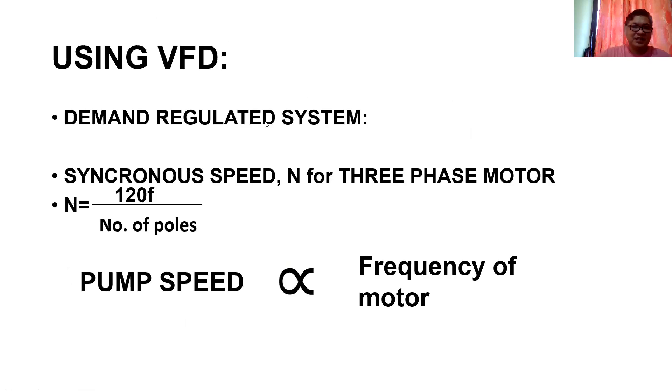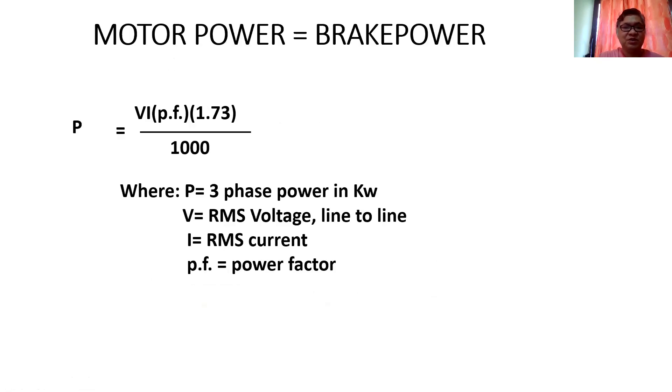Using VFD, we have what we call a demand regulated system. In pumping, we would like to have a constant pressure in our pumping system using VFD and transmitters. The speed is equivalent to N equals 120 times the frequency divided by the number of poles. For a three-phase motor, the number of poles is normally four. Pump speed therefore is directly proportional to the frequency of motor.